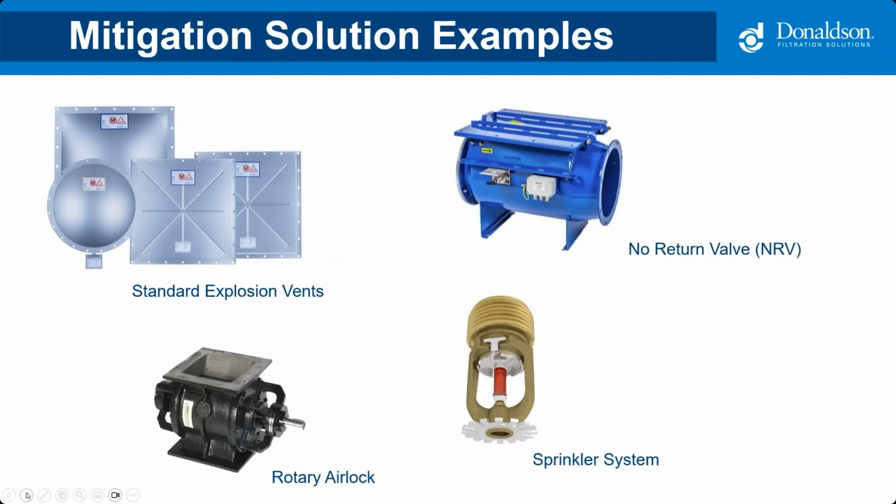One thing about the no return valve, it is going to add additional static to the system, typically in the 1 to 2 inch range. So your fan has to be sized for that. So if you're going back and retrofitting, you may have to change your fan out as well to keep your performance of the system.